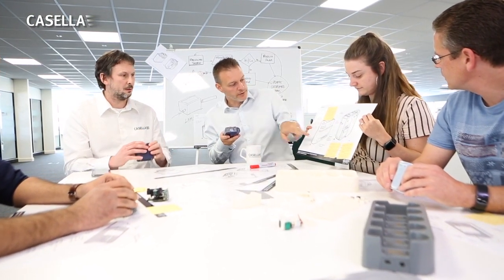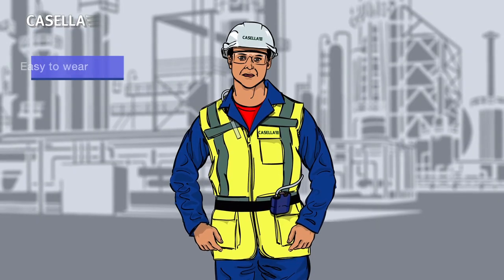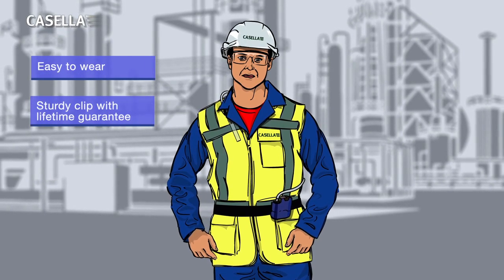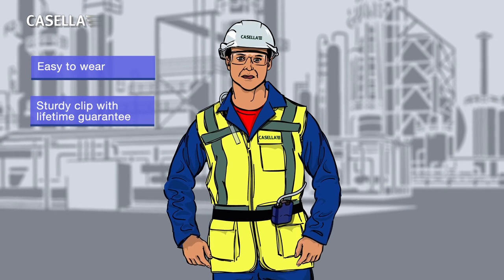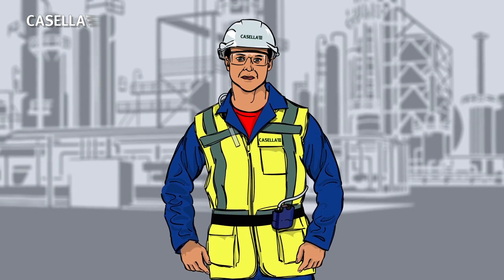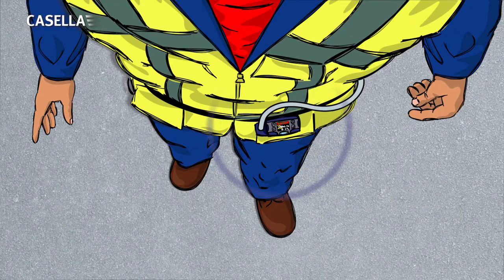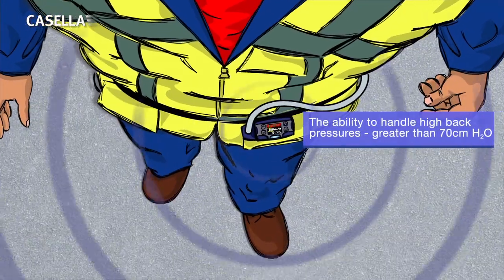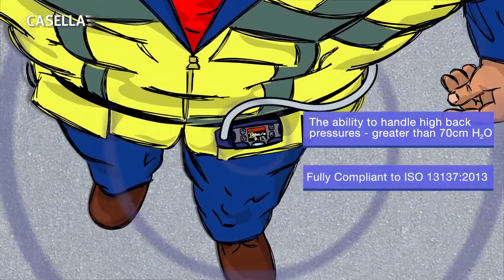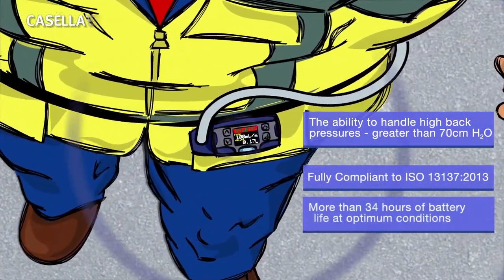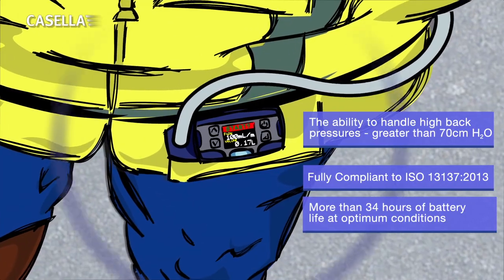The intrinsically safe design of the pump and remote operation via the Airwave app makes it ideal for modern-day sampling requirements. The sophisticated control mechanism allows users to take readings at precise flow rates without drifting away from their set point, saving time as runs won't need to be repeated. The new generation battery lasts for more than 4 8-hour shifts.